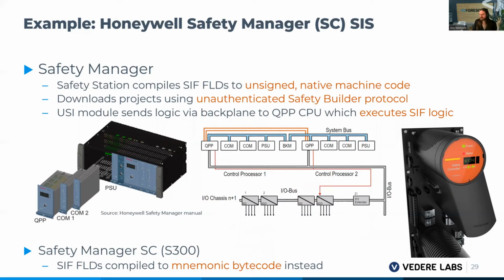After receiving this download, the communication module sends it over the backplane to the CPU module, which executes it directly on the CPU, leading to unconstrained code execution in the heart of this safety controller.